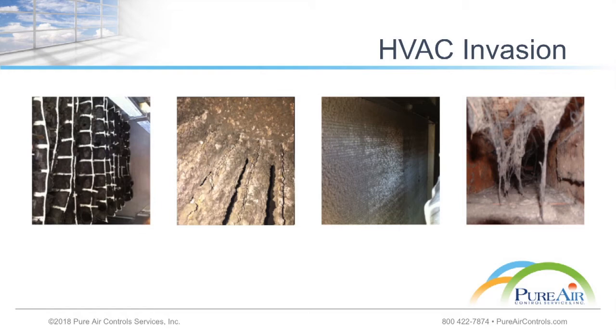If your HVAC system has issues with bypass, maybe the filters are an issue, even if the hurricane caused damage to your HVAC and now allowed for that return air to bypass right into the supply airstream, you have the ability to contaminate the rest of the building. That's a big issue we see every time there's a water event in a building. If things are properly addressed, it can be avoided, but it's very important because an isolated problem can turn into a building-wide problem.